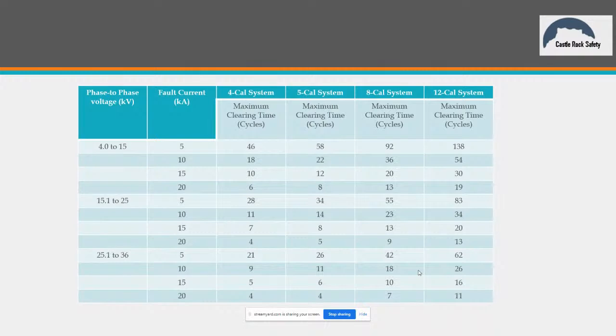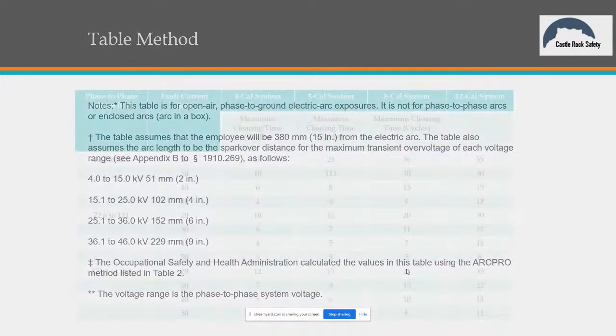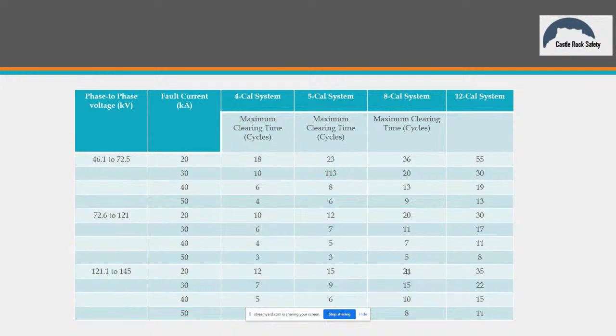And that's due to it being open air, correct? Correct. It's due to it being open air, and it's also based on fault current and clearing time, open air, distance. But yes, open air is a big difference. It's a lot different than me standing 18 inches in front of a panel board. Absolutely, I agree. There are a lot of grounded parts in there too. Exactly. And then guys, if you go up to the higher voltages, right?